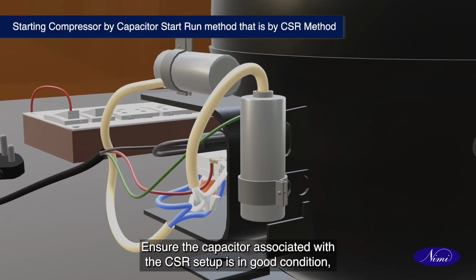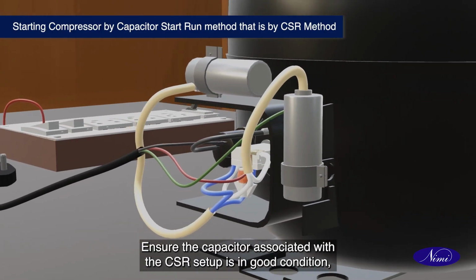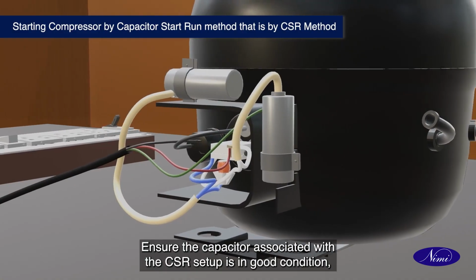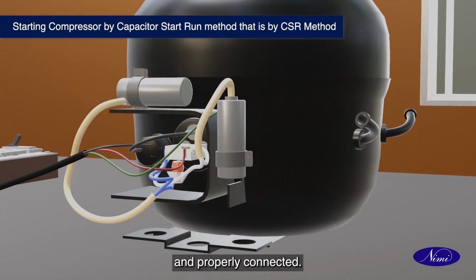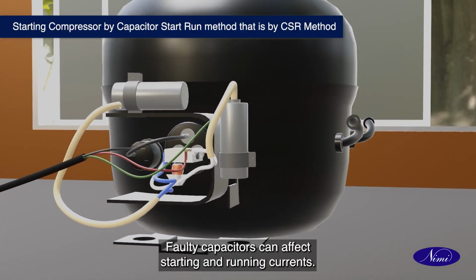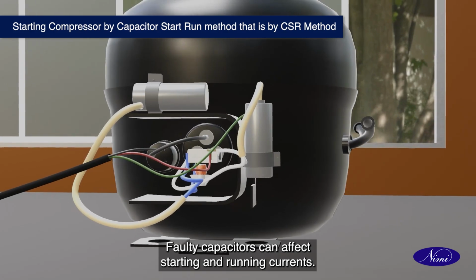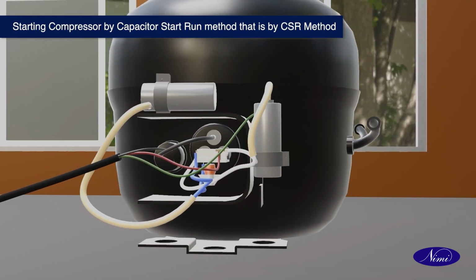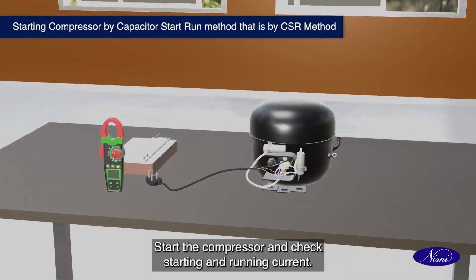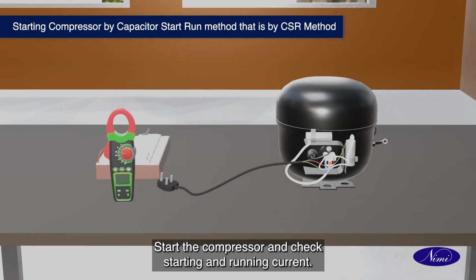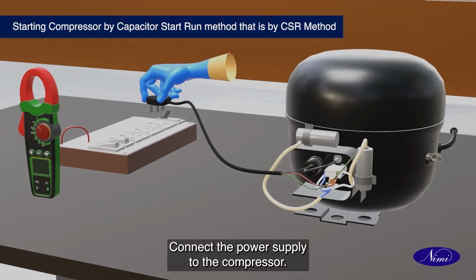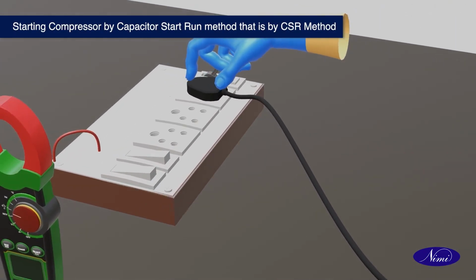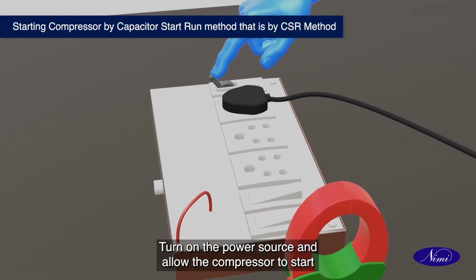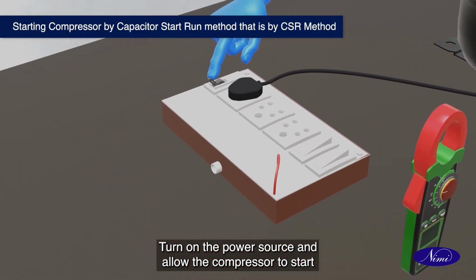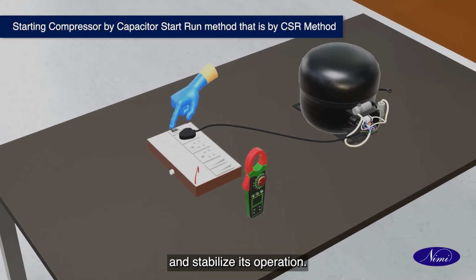Ensure the capacitor associated with the CSR setup is in good condition and properly connected. Faulty capacitors can affect starting and running currents. Start the compressor and check starting and running current. Connect the power supply to the compressor. Turn on the power source and allow the compressor to start and stabilize its operation.